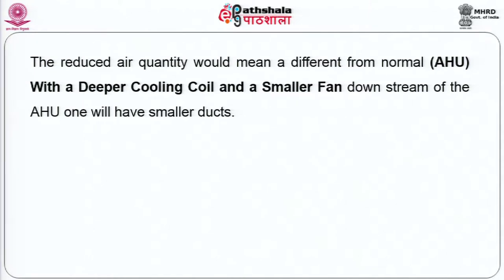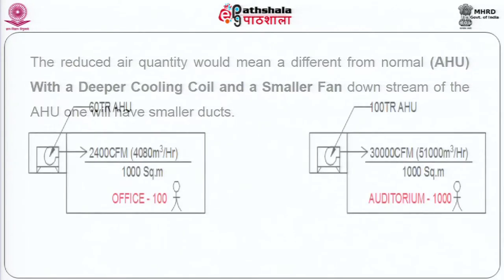This reduced air quantity would normally mean a different from normal air handling unit, and the basic difference will be that the cooling coil inside the air handling unit will be deep. In other words, it has to be able to hold air to it for a longer period of travel, so that it can pull out some more moisture which is contributing to the latent load.